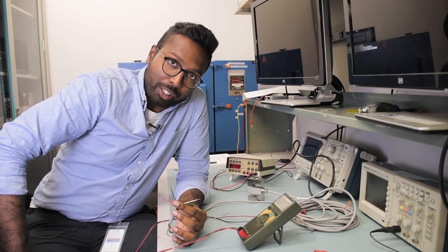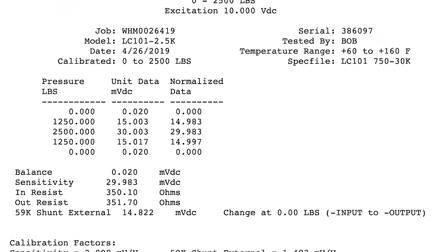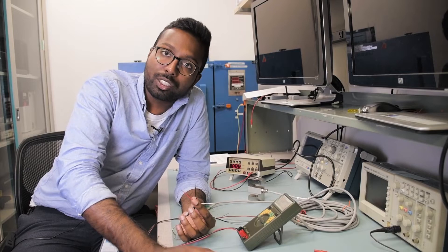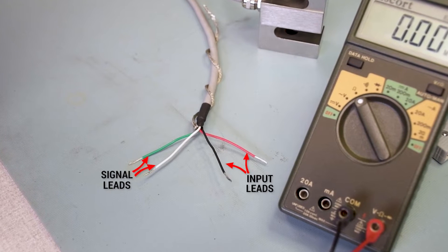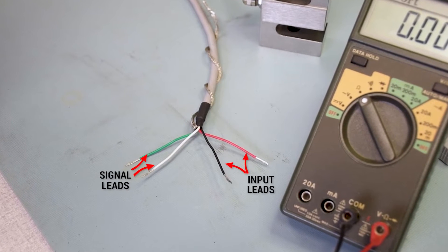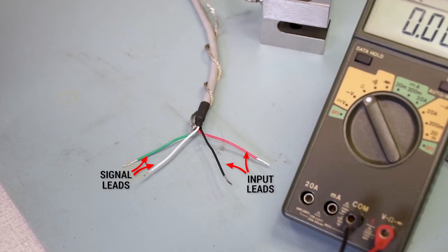If you look in the calibration certificate that you receive with a load cell, you should see input resistance and output resistance values. Input resistance is the resistance across the two input leads that go into the load cell, and the output resistance is the resistance across the signal leads—the signal that comes from the load cell.